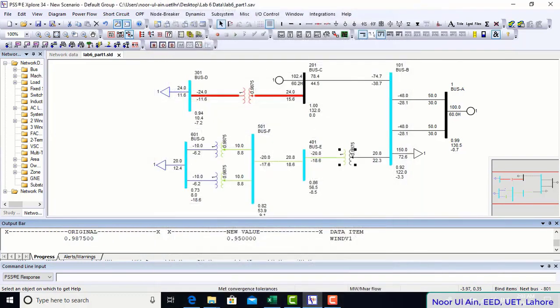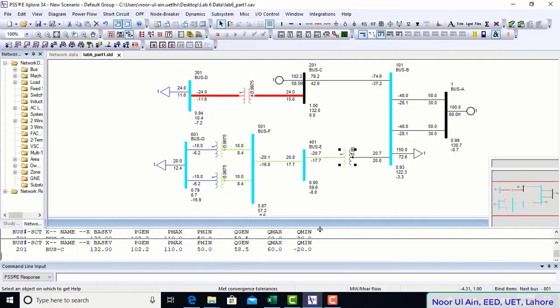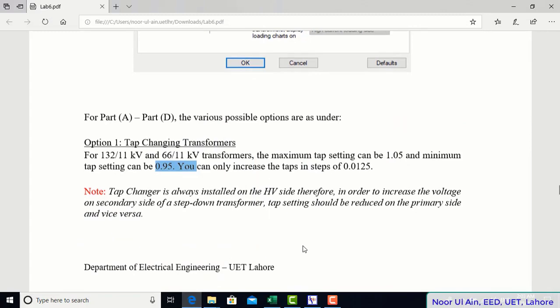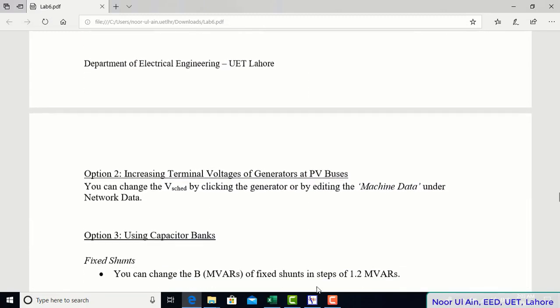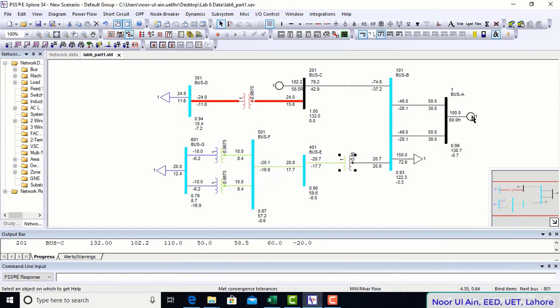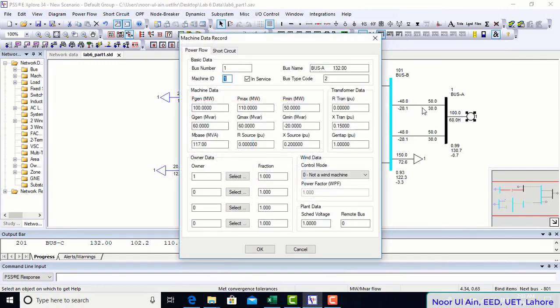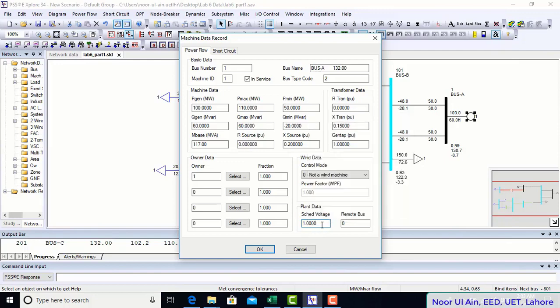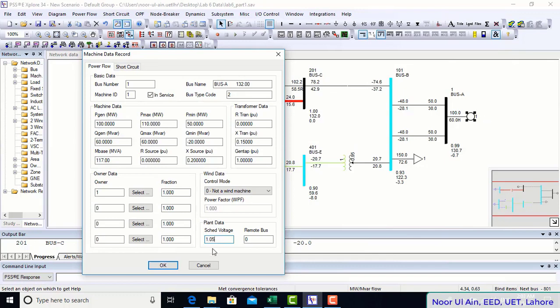Okay, I will try with this option 0.95 and then again solve the system. Still, I haven't achieved any desirable results. So I will try the second option. The second option is, you can increase the scheduled voltages at your machine buses or the PV buses. Like, you can change this scheduled voltage up to 1.05, right?